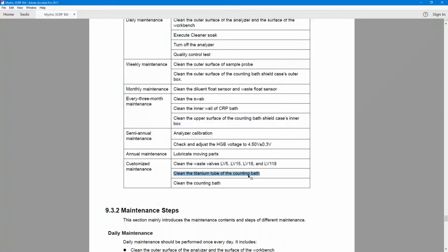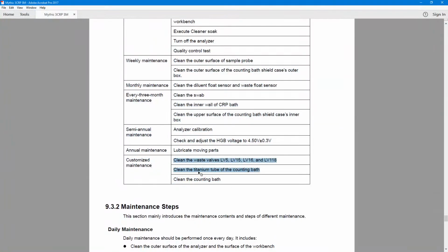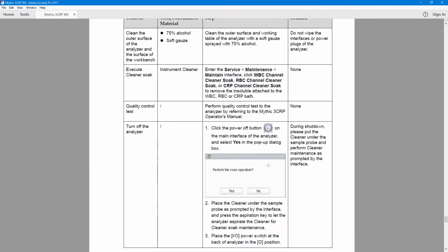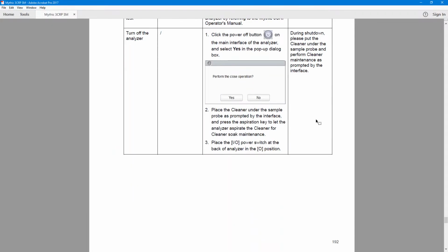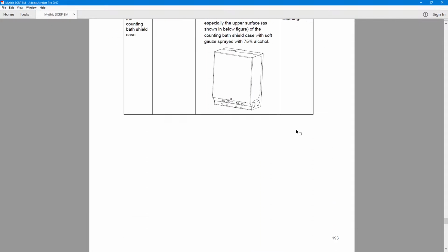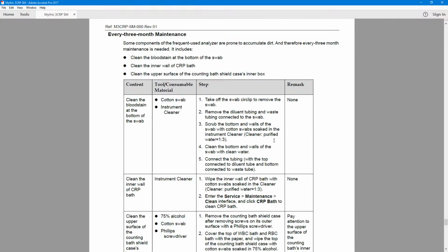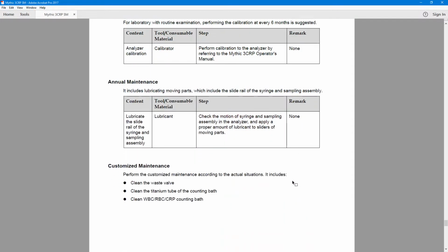Cleaning the titanium tube of the counting bath may be necessary, but not always. I would say that this is necessary when the analyzer was not used for a long period of time and someone left the reagents inside. Clean the counting bath, the same thing. If someone left the reagent and the device was not used, then you need to perform that. And actually in the service manual, there is a step-by-step instruction on how to perform all those activities.